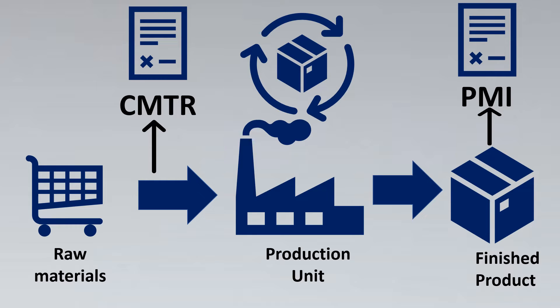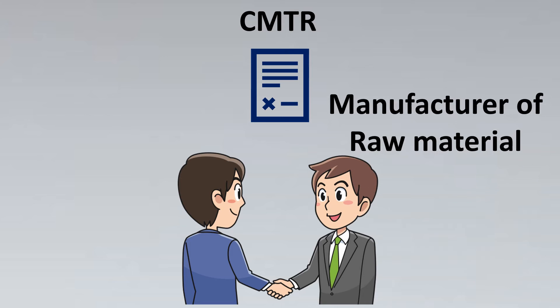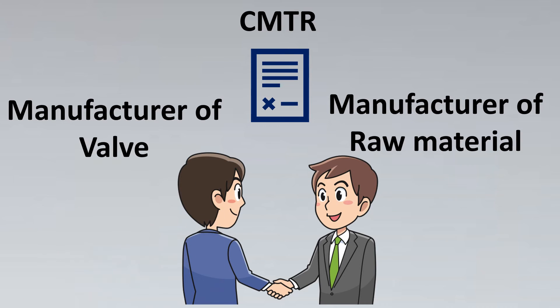Now let's look a bit deeper into CMTR, because it is further subdivided. Before we get into its divisions, let's cover the concept of when and who gives the CMTR. Basically, the Material Test Report is given by the manufacturer of the raw material to the manufacturer of the valve. For example, if the valve requires Hastelloy or SS316L, the raw material vendor would give a certificate stating that they have supplied that particular grade only.